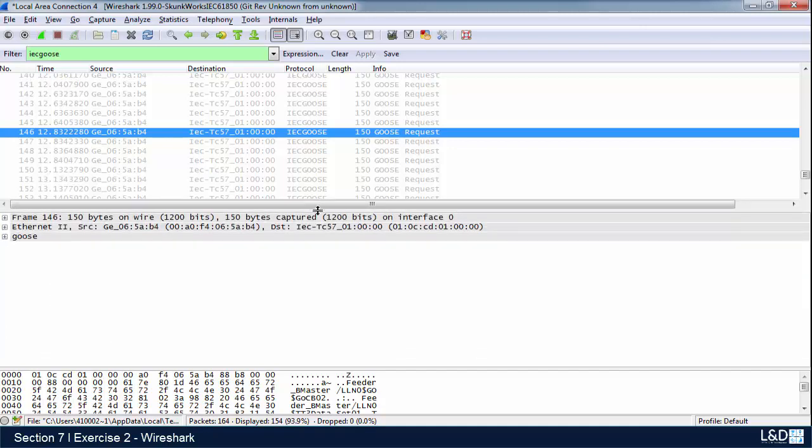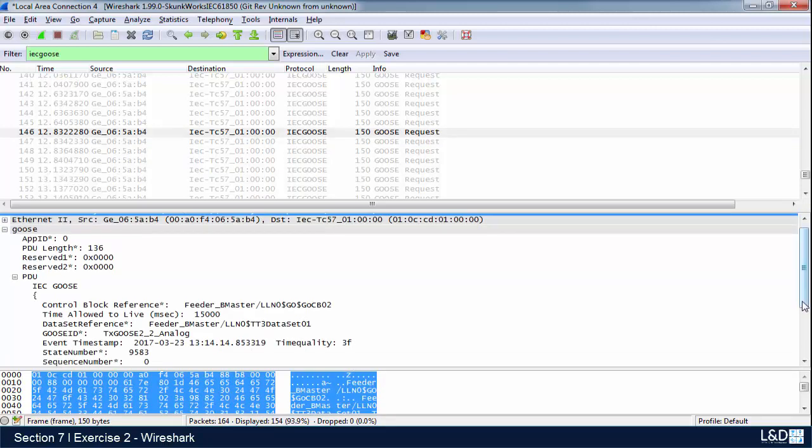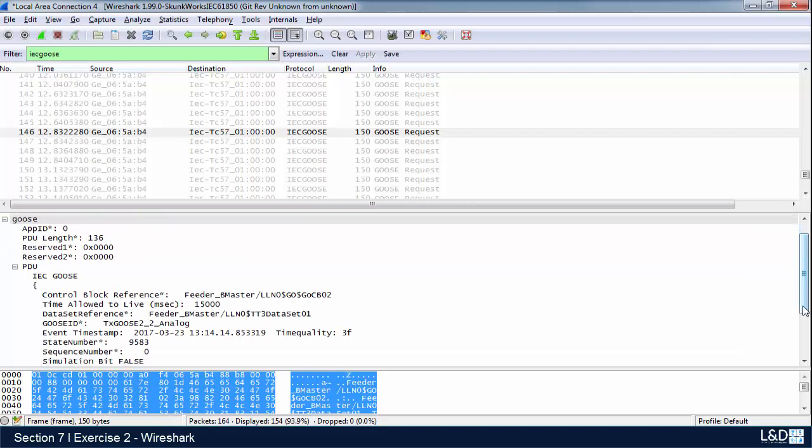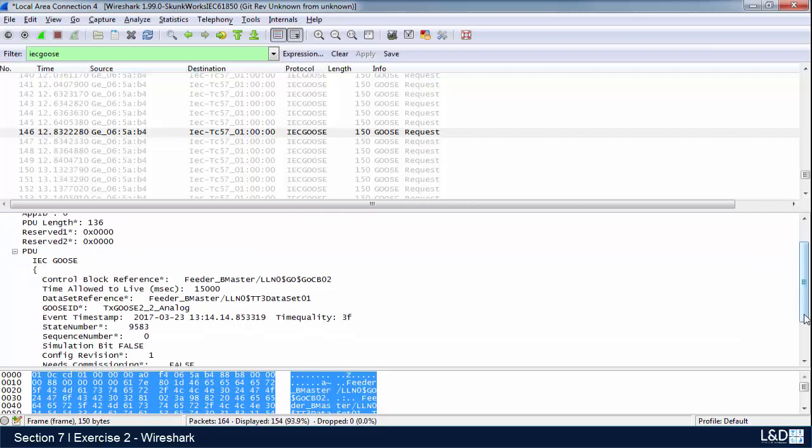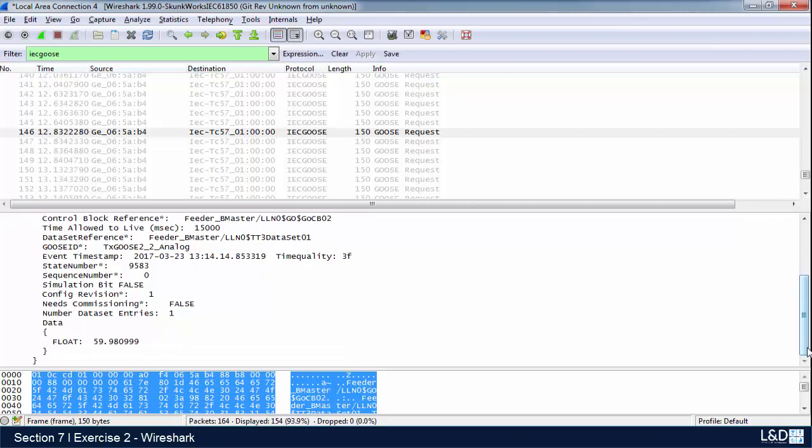I'll pick a signal and let me just slide this up a little bit so we can see what's going on. What's interesting to us is this subfolder GOOSE, and we can come down here and see what this information is. In this case, we have the GOOSE message from our feeder B that we set up. It's the analog signal, and we can see this is the frequency that we're monitoring.